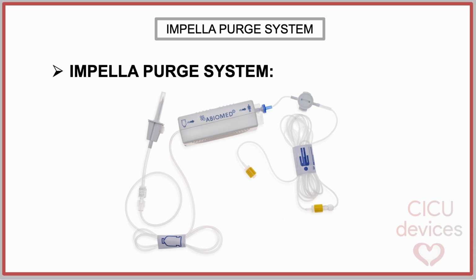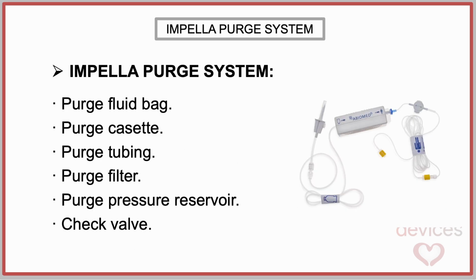The Impella purge system consists of a set of integrated components designed to ensure stable purge flow and pressure at the motor housing. These elements include the purge fluid bag, the purge cassette, the purge tubing, the purge filter, the purge pressure reservoir, and the check valve. Thus, the purge fluid flows through the circuit, circulates around the motor shaft, and finally exits through a small gap located between the motor housing and the impeller, creating a continuous barrier that prevents blood from entering the motor.